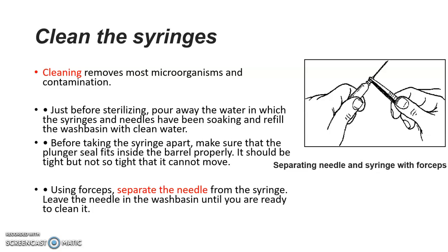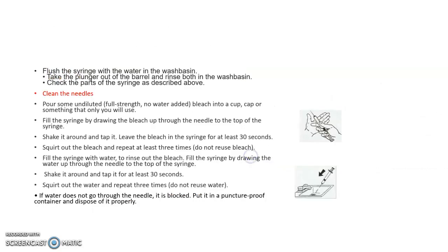Before taking the syringes apart, make sure that the plunger seal fits inside the barrel properly. It should not be too tight or too loose that it cannot move. It should be tight but not so tight. Then using forceps, we should separate the needle from the syringe and leave the needle in the wash basin until you are ready to clean it.